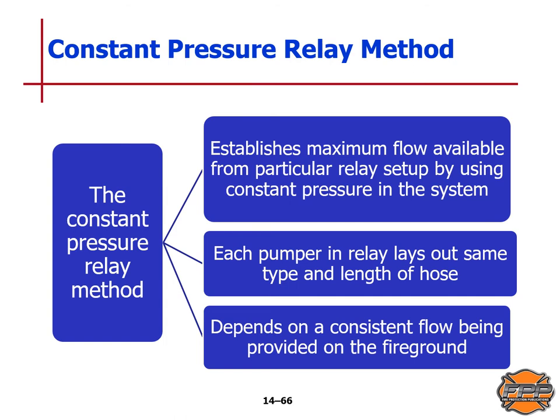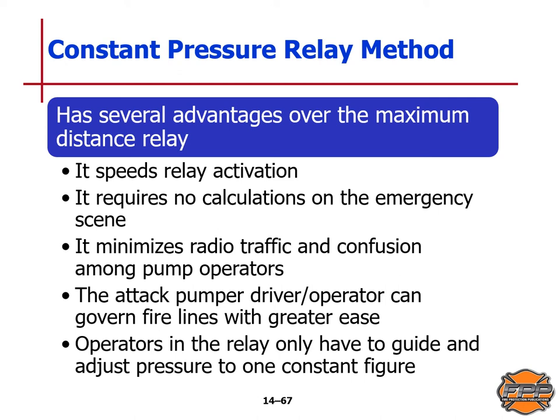The constant pressure relay method establishes the maximum flow available from a particular relay setup by using constant pressure in the system. Each pumper in the relay lays out the same type and length of hose, and this method depends on a consistent flow being provided on the fire ground. This method has several advantages over the maximum distance relay: it speeds relay activation, requires no calculations on the emergency scene, minimizes radio traffic and confusion among pump operators, allows the attack pumper driver operator to govern fire lines with much greater ease, and operators in the relay only have to guide and adjust pressure to one constant figure.